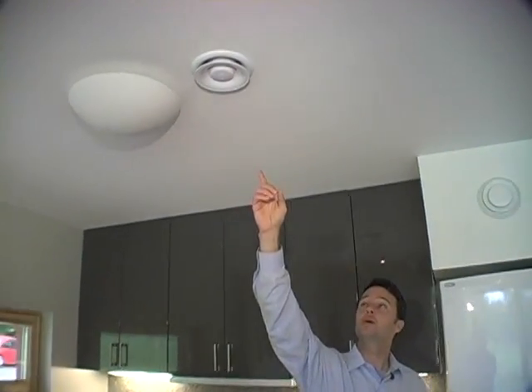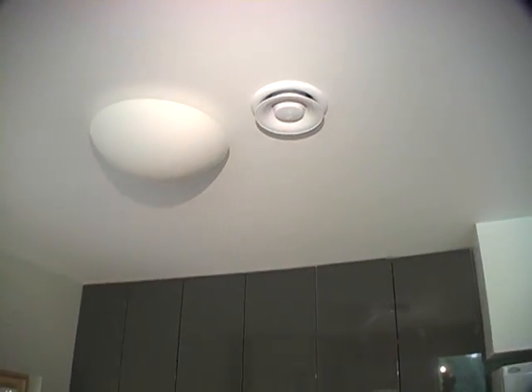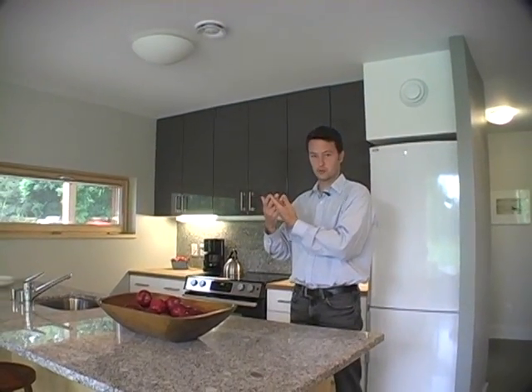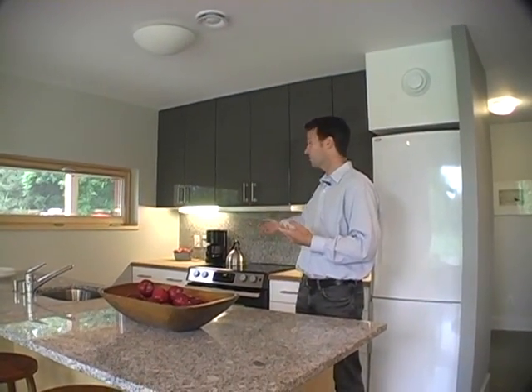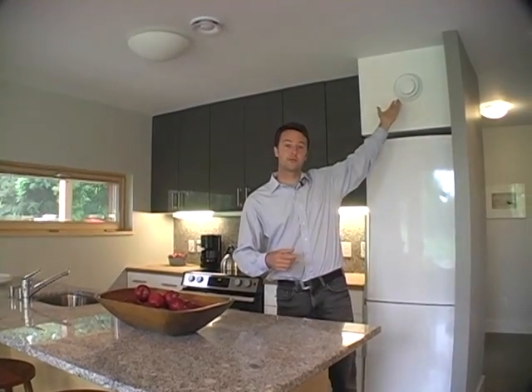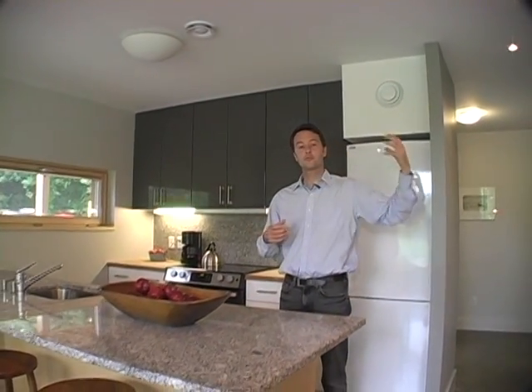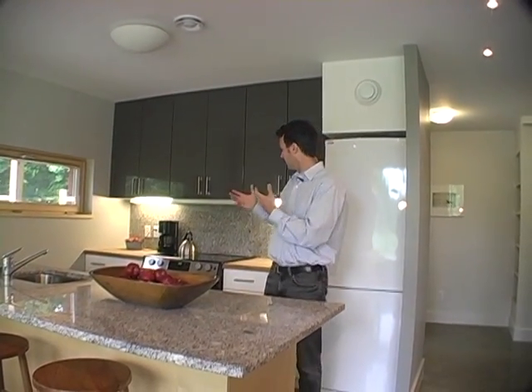This port allows air to be drawn out of the kitchen with the moisture and smells we create by cooking, directly from the range or from the range hood exhaust up there, and it draws it out through the heat recovery ventilation system. The benefit is that all the moisture and heat we're creating from the range gets transferred back into the house in the fresh incoming air stream. So we're always recuperating the air while still bringing in fresh air.